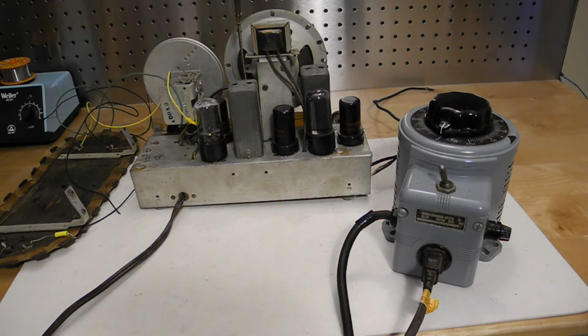It allows you to slowly power up from 0 volts up to the rated voltage. Power it up slowly while watching for any unusual signs like heat, smoke, or arcing. If you have an AC meter, use it to monitor the current while slowly bringing up the voltage. Note that a variac does not isolate, so you should use an isolation transformer in addition to a variac.